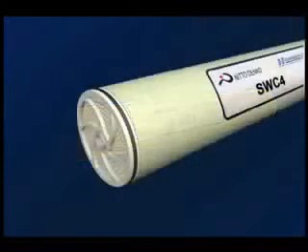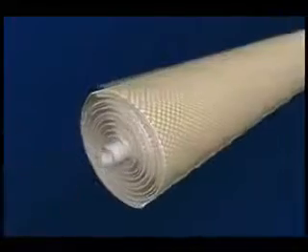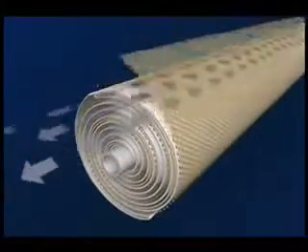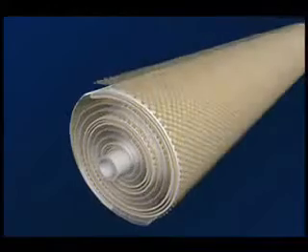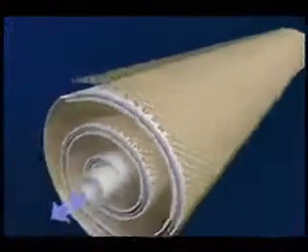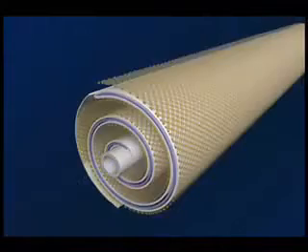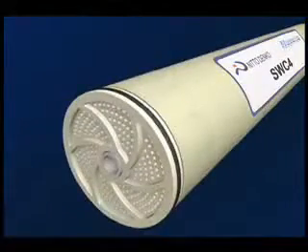With the back of the membrane completely sealed to the edges of the permeate spacer, the feed water is forced through the feed channel spacer contacting the front or barrier layer of the membrane. Clean water, or permeate, passes through the membrane surface into the permeate channel and then flows in a spiral direction to the center of the element and is collected into the core tube.